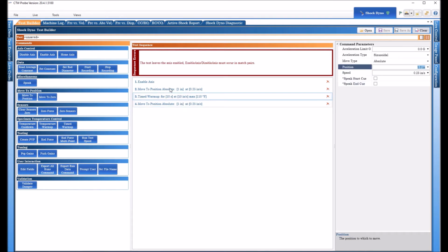So basically the actuator is going to go from here, and it won't update until I save it, but that's a 1/2 inch, and this is 1 inch, and we're going to start our test from here. Now everything is absolute, so that is 1 inch from the bottom of the actuator, for where it sits at rest, up 1 inch. So once that is done, we're going to go ahead and start recording.